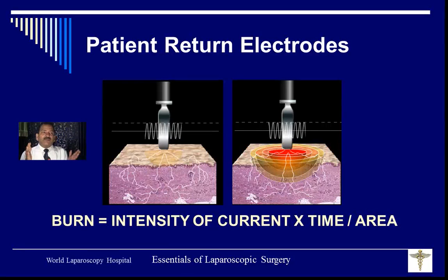If you will see, there are two types of machines available in the market: one is 250 watt and another is 400 watt. If you want to do simple laparoscopic cholecystectomy or hysterectomy, then a 250 watt machine is sufficient. And if you want to do operative hysteroscopy or TURP, then 250 watt will not work; you need a 400 watt machine. Because in TURP or hysteroscopic myomectomy, you have to work underwater, and underwater, the intensity of current required is more. That's why 400 watt current is used.